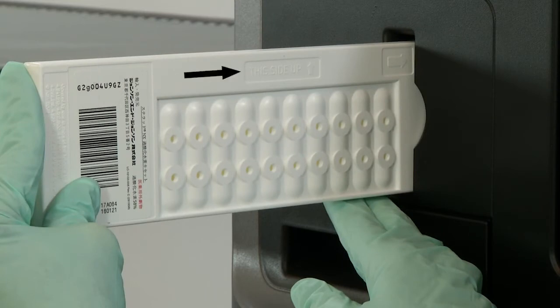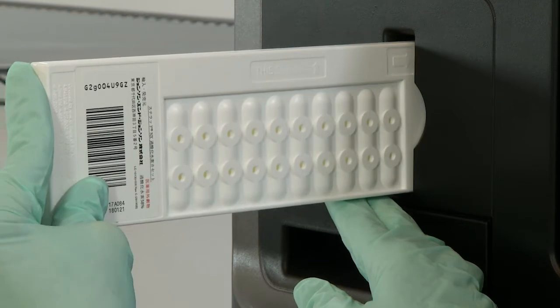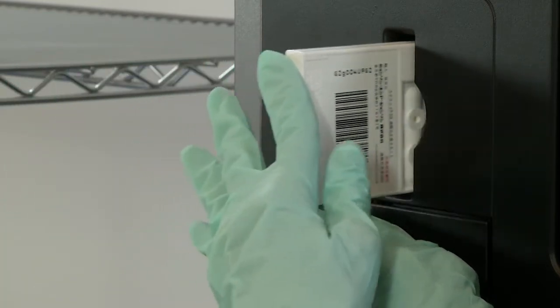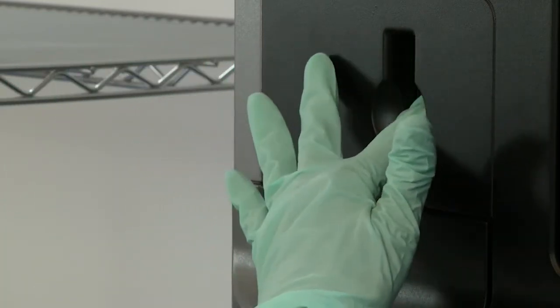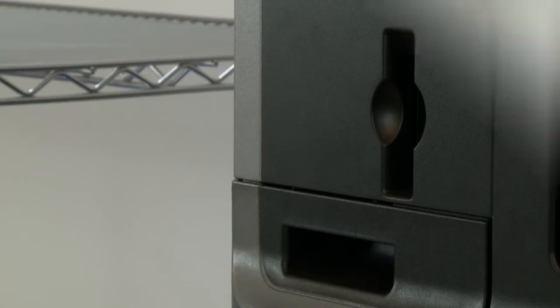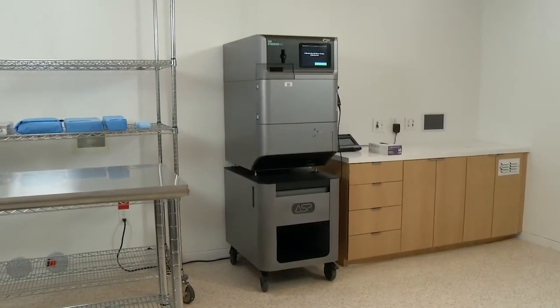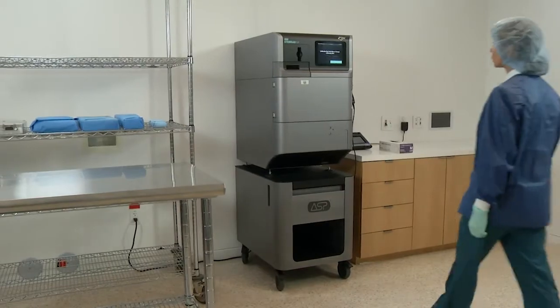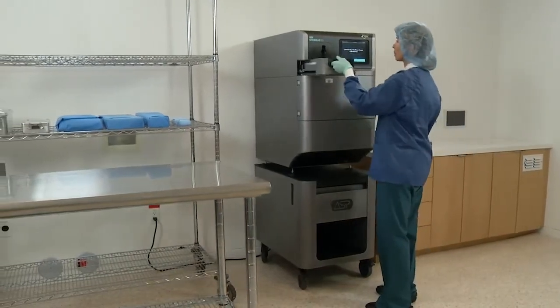The message indicates this side up, and the directional arrow points toward the sterilizer. Insert the cassette into the cassette slot until the system detects and pulls the cassette in. Do not use excessive force to insert the cassette. When a cassette is empty, the sterilizer automatically moves it to the cassette disposal box in the collection drawer.